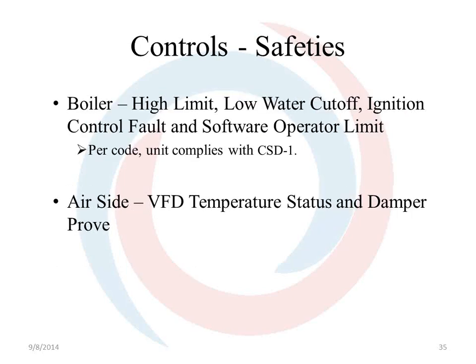On the air side, the VFD temperature status prevents the VFD from running in temperatures below 25 degrees. When the temperature is below 20, the controller enables a small electric heater within the VFD enclosure to bring the box temperature to an acceptable level. The electric heater is about 150 watts, and for larger horsepower motors and VFDs, the heater may be 300 watts. Damper proving switches also give the damper 30 seconds from the time the dampers are told to open before shutting the unit down, the boiler and the VFD after the initial failure.